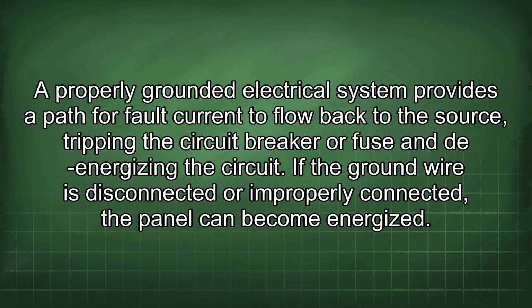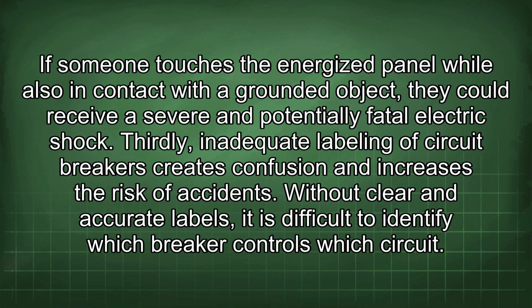A properly grounded electrical system provides a path for fault current to flow back to the source, tripping the circuit breaker or fuse and de-energizing the circuit. If the ground wire is disconnected or improperly connected, the panel can become energized. If someone touches the energized panel while also in contact with a grounded object, they could receive a severe and potentially fatal electric shock. Thirdly, inadequate labeling of circuit breakers creates confusion and increases the risk of accidents.